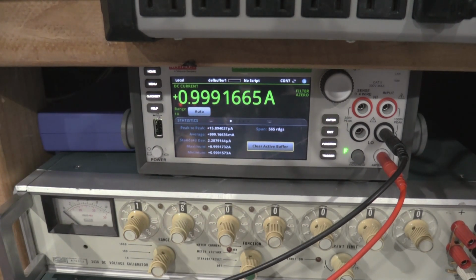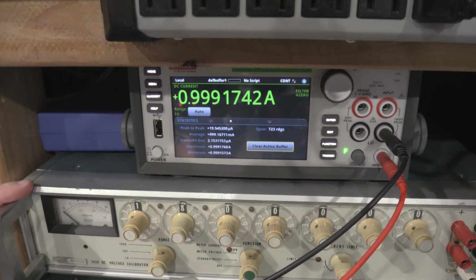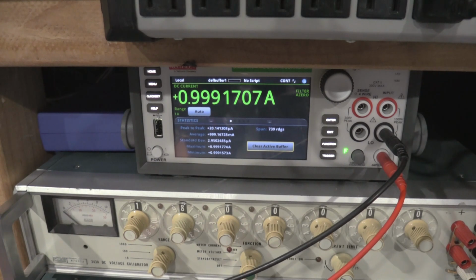The service manual would like a 3 ppm unit. The 7510 is a 1.4 ppm unit. Or, I'm sorry, a 30 ppm unit. The 7510 is a 14 ppm unit, so I actually have twice the accuracy I need, even though we're getting down into the splitting hairs level of territory. For the input voltage, I am going to need the 343 because I have to do all of these with a very stable 10 volts. And my Keithley power supply was good enough for testing, but not good enough for doing the calibration.